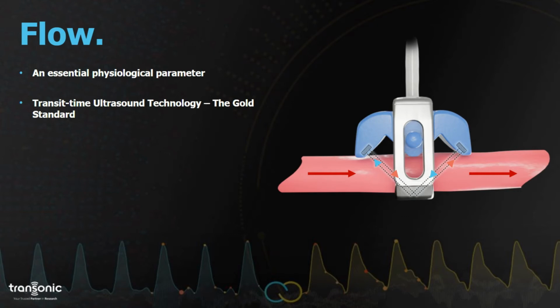What's happening here is we're sending an ultrasonic signal that transits through the vessel as we move from right to left, bounces off that reflector, and then goes over to the left side of the probe, where it is measured by a receiver. At the same time, we're sending a signal in the opposite direction, with the blood flow. Again, it's a very simple principle. Our technology monitors the time it takes for this signal to transit the lumen, of course, transit time. And from this we're able to derive a very accurate absolute volume.